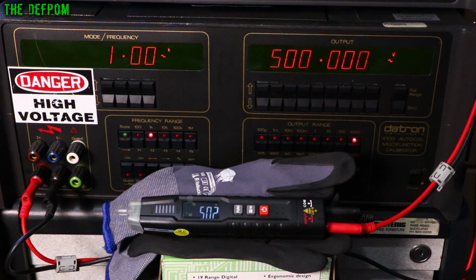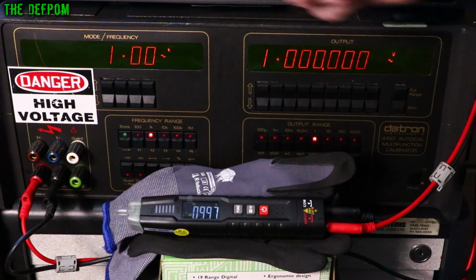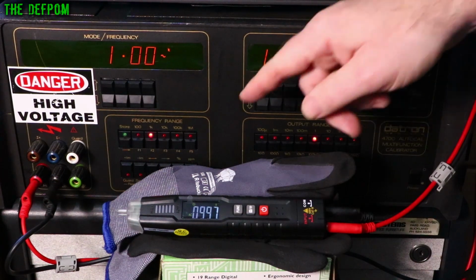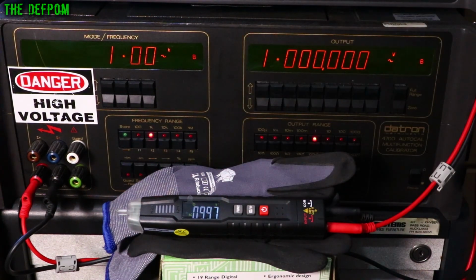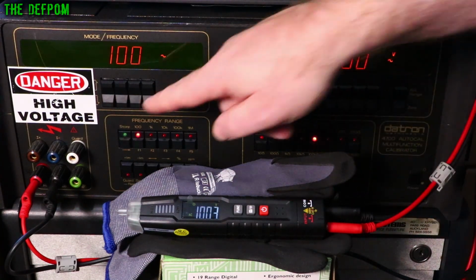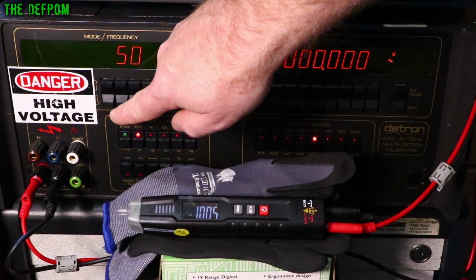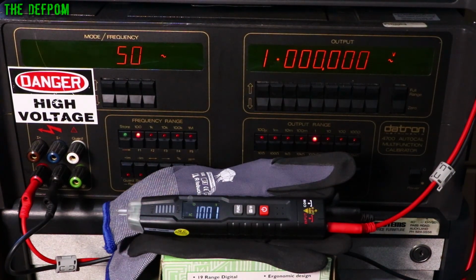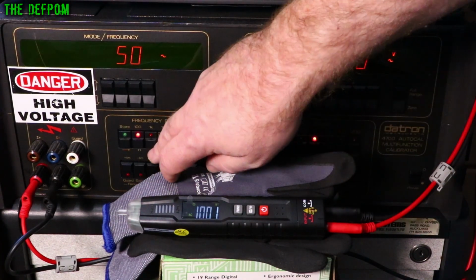Interesting. Let's check the frequency response out. So we're at 1 kilohertz right now, 1 volt. Let's go down to 100 hertz. That shouldn't be a problem for it. Yep, that's fine. 3 counts high. Let's go down to 50 hertz. 1 count high.